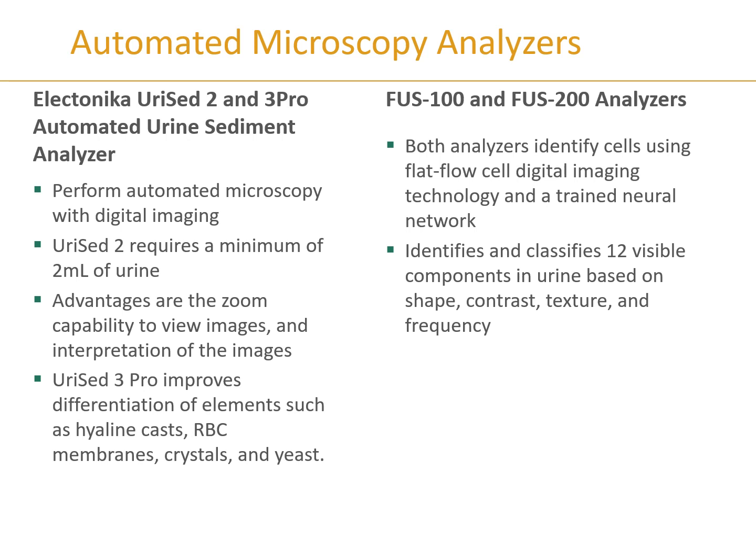The FUS 100 and 200 analyzers identify cells using flat flow cell digital imaging technology and a trained neural network — a newer category of imaging. It identifies and classifies particles into 12 visible components based on shape, contrast, texture, and frequency of the particular particulate in the urine sample.